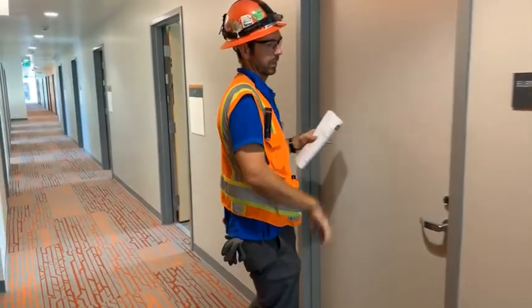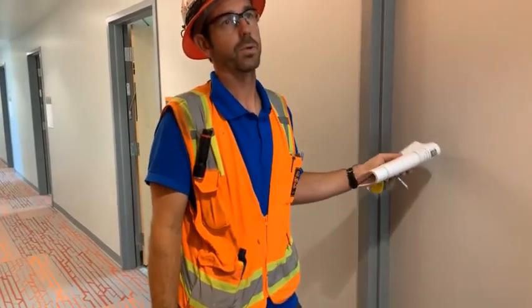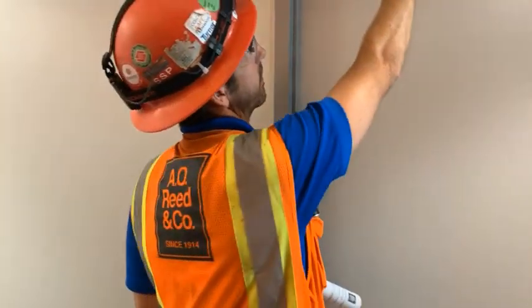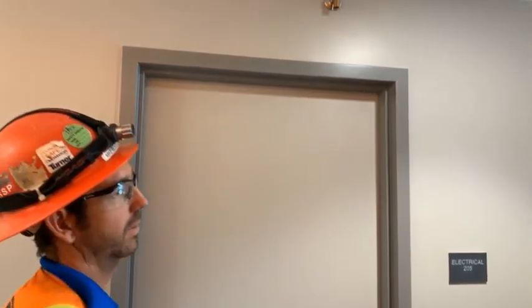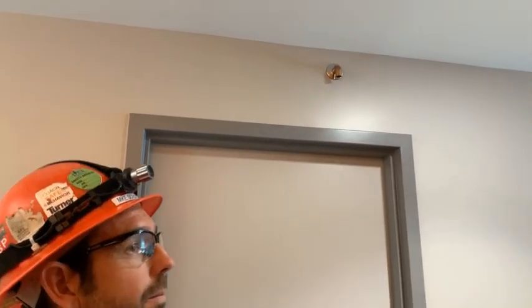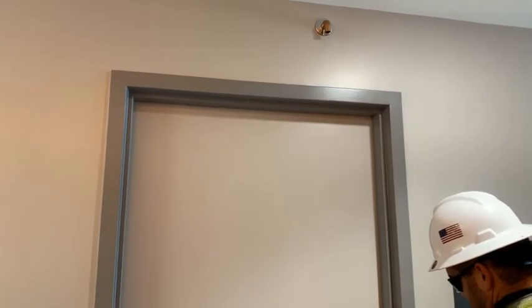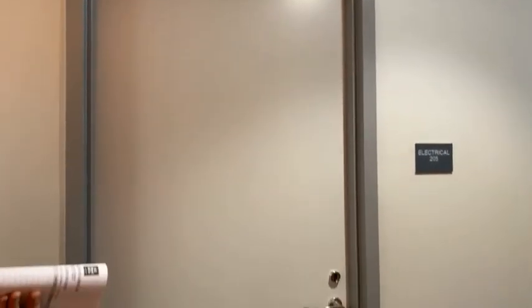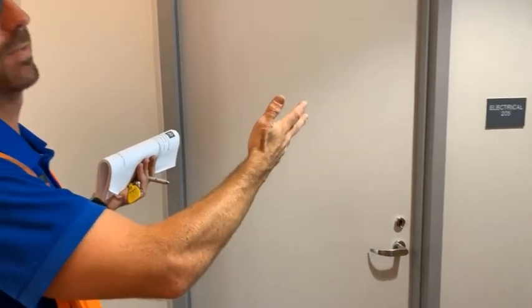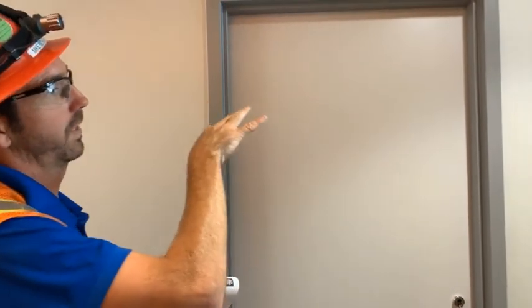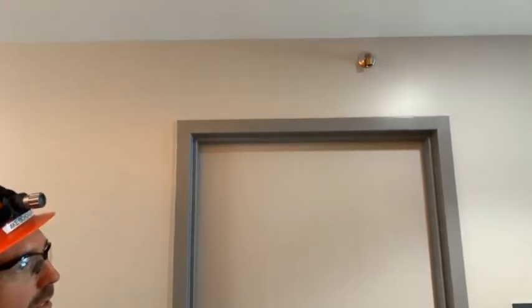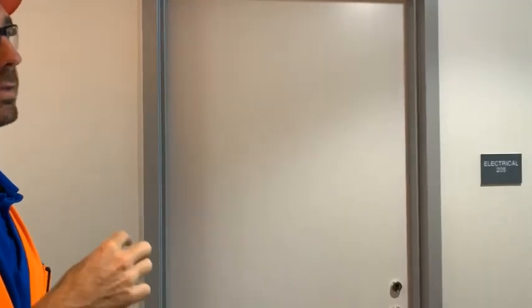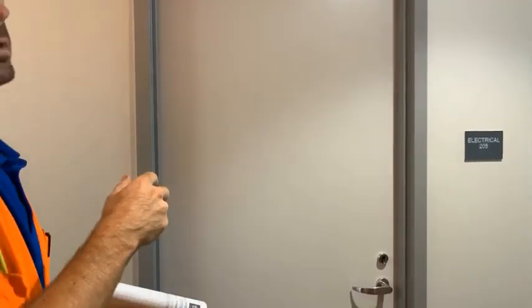So this is our electric room. This is the main electric room for the 2nd floor. We do have tattletales here, so there's a drip pan for the fan coil. Yeah, I don't think it's a turnover key yet. It's just a different core than they would get. No, I remember. It's a typical room unit fan coil. So that's the overflow tattletale, yeah. There are also condensate switches in the drain pans as well, in the main drain pan, the primary drain pan. Are they a float that's in the pan? Yes.